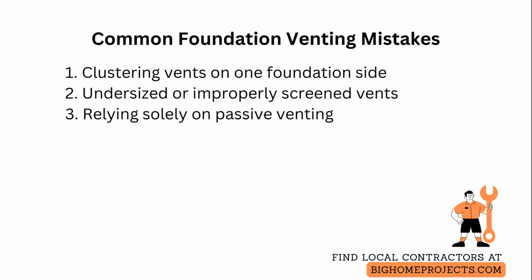Common mistakes include clustering vents on a single face of the foundation, which prevents cross-ventilation and creates high humidity pockets. The fix is to relocate vents or add matching vents on the opposite side to balance airflow.